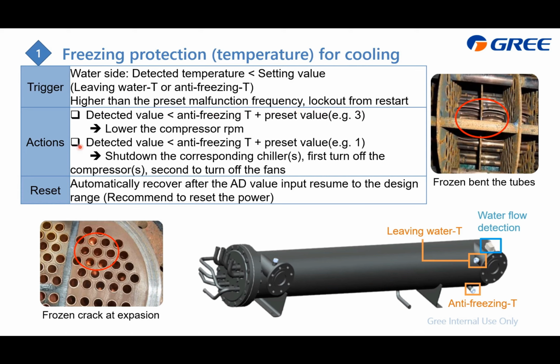And before that, we also have the freezing protection, which is if we detect the temperature is lower than the setting value plus the preset value, for example 3, we lower the compressor RPM. This is for the inverter. For the on-off series, we only have this one: if we detect it lower than this, we need to shut down the corresponding chiller, first turn off the compressor and then turn off the fans. It will automatically recover if we detect the AD value resume to the desired range. And of course, we recommend to reset the power.